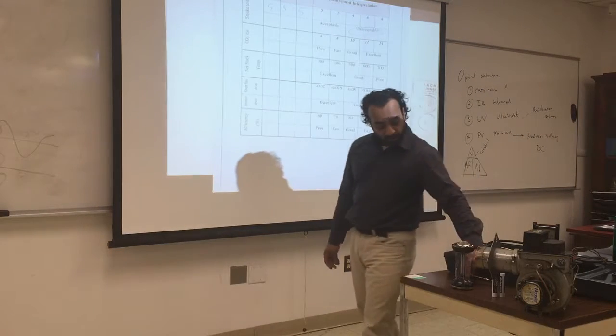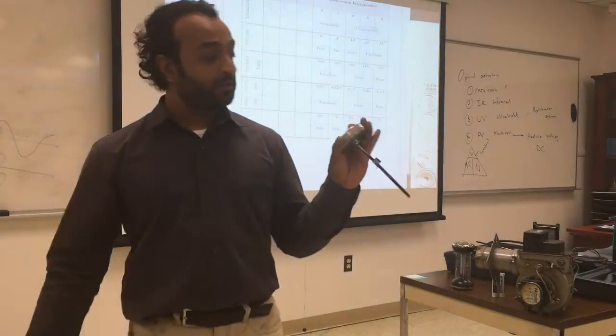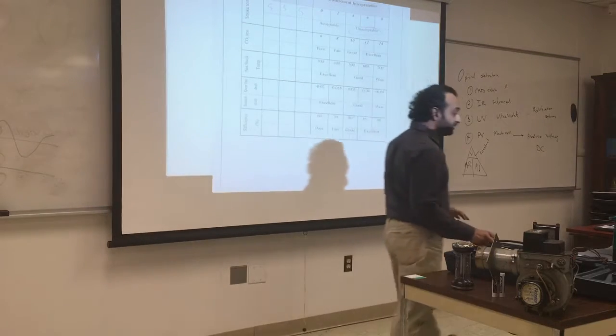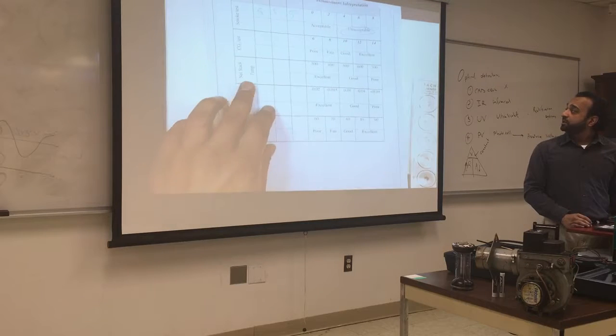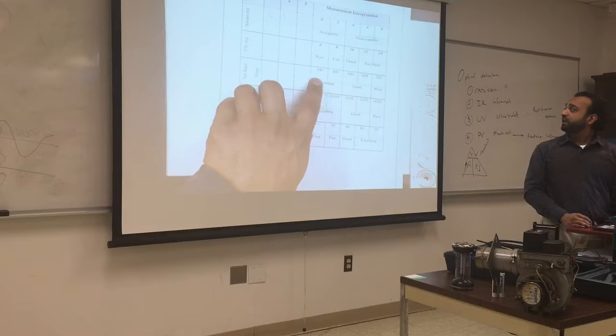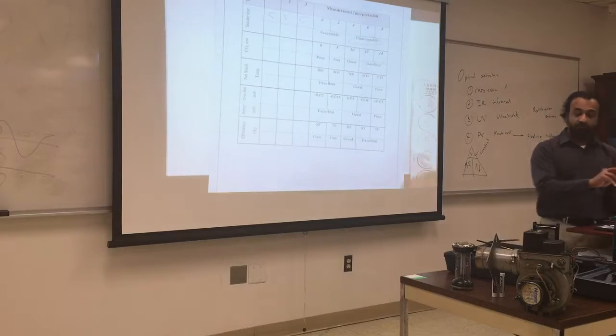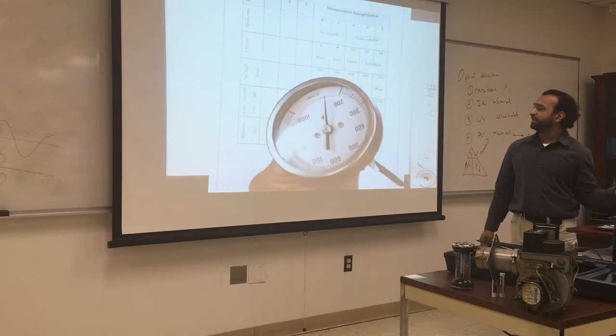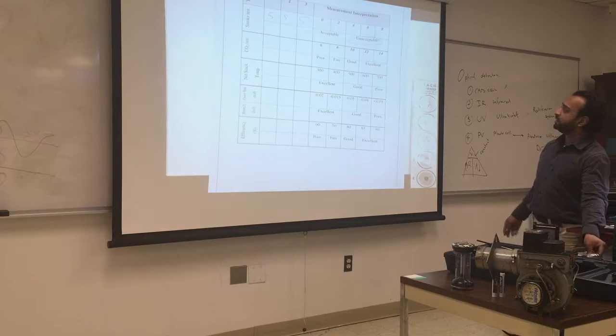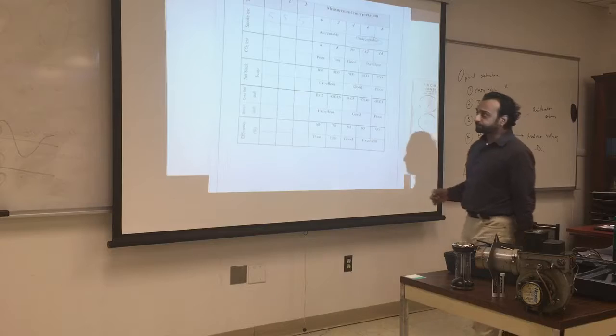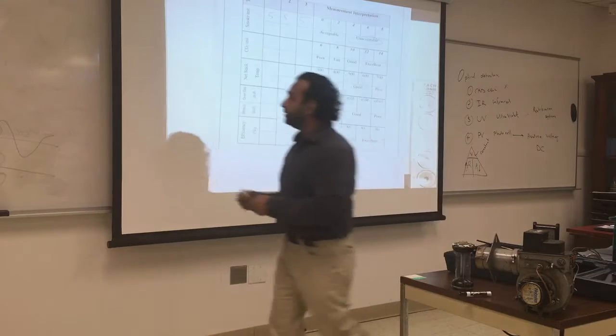Next step, temperature is the third thing. We will stick this on the burner at the breech, there's a hole, you leave that in the hole and wait for it to stabilize. Whatever number we get once it's stabilized, we will do the net stack temperature. We do it again, take it out, put it back again. It should be around 300 or 400. That says net, not gross. Net will be whatever number we get from the thermometer, we will subtract the ambient temperature. We set down around 50 and 70, so we subtract that number we get from the thermometer, and that will be your net stack temperature.